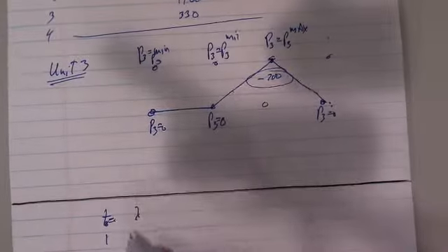So my lambda values come out to be 1.7, 5.2, 11.0, and 3.3. So those are the new values. Lambda: 1.7, 5.2, 11, and 3.3. And they were obtained because of the load. There was no generation on, therefore the dq dp is positive.